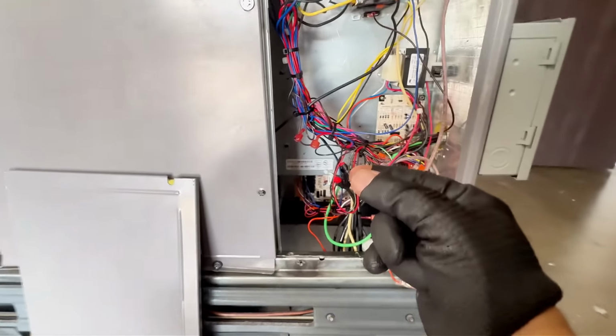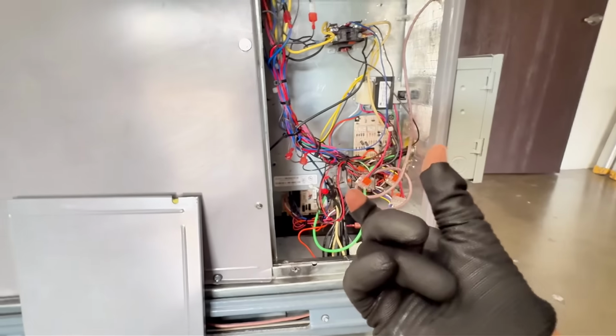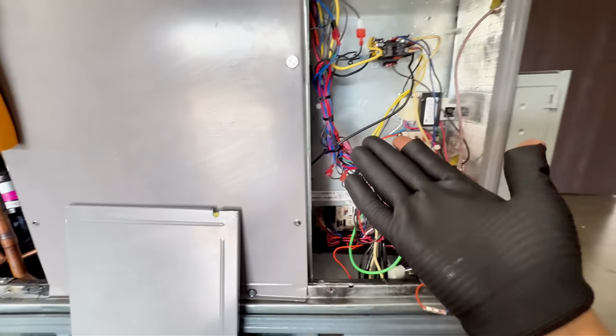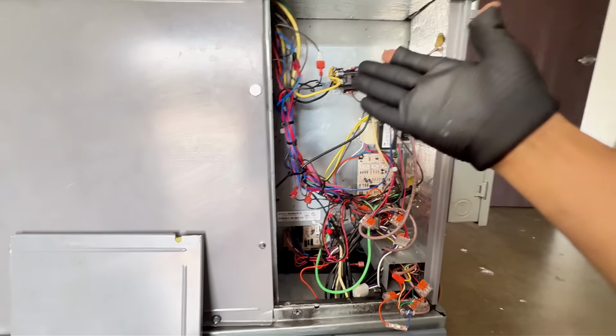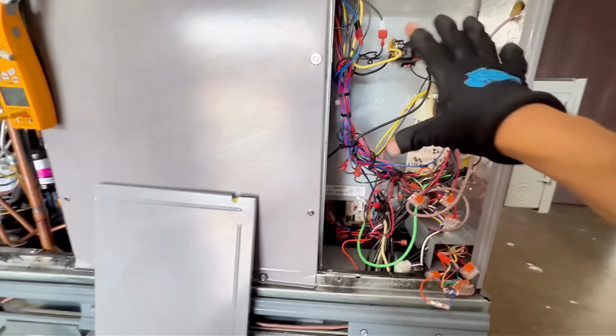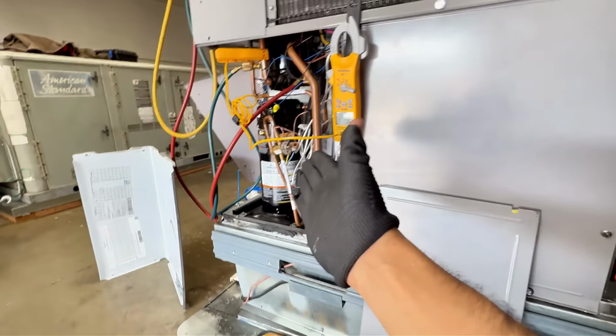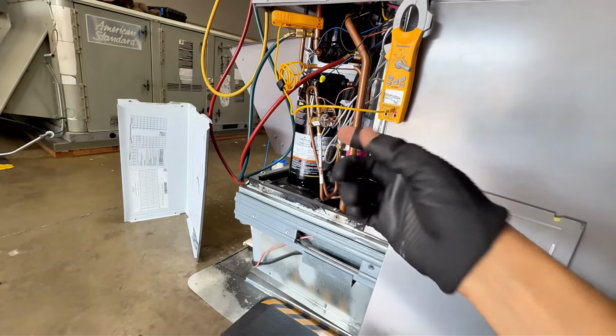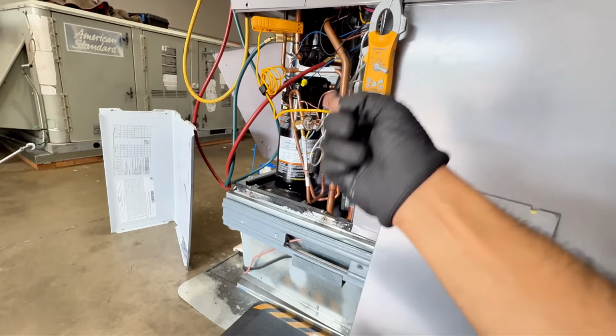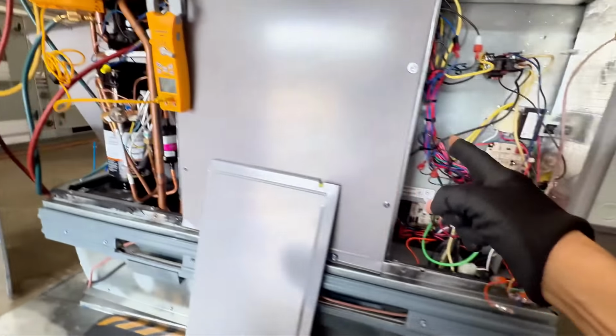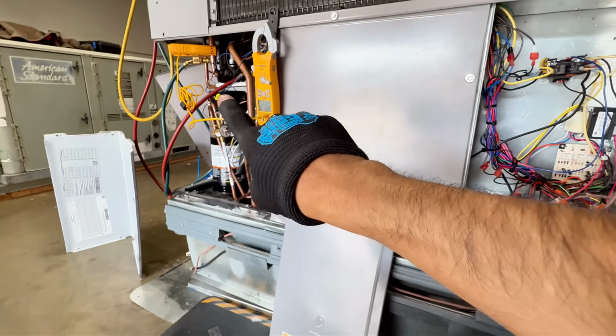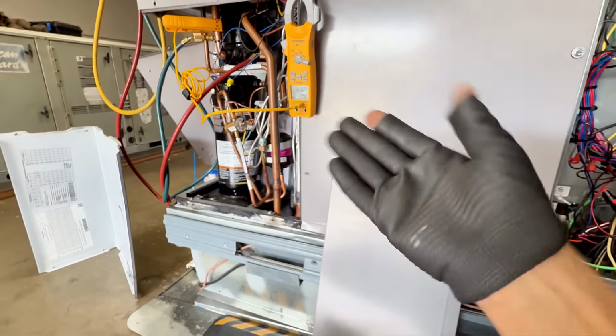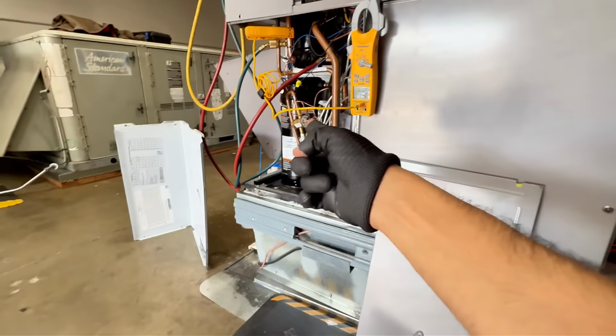If your fuse popped, then hot and common are touching somewhere, or hot is rubbing on the metal, or maybe the contactor coil load is bad. But once you figure out the low voltage, okay, my compressor's not turning on. Maybe it's on thermal overload. Maybe I'm low on refrigerant. But you wouldn't even get the compressor to turn on if you're low on refrigerant, because my pressure switch would be open. 24 volts will never make it back. And that's the thing, a lot of systems don't have pressure switches, so it could still be off on thermal overload. It could be really hot.